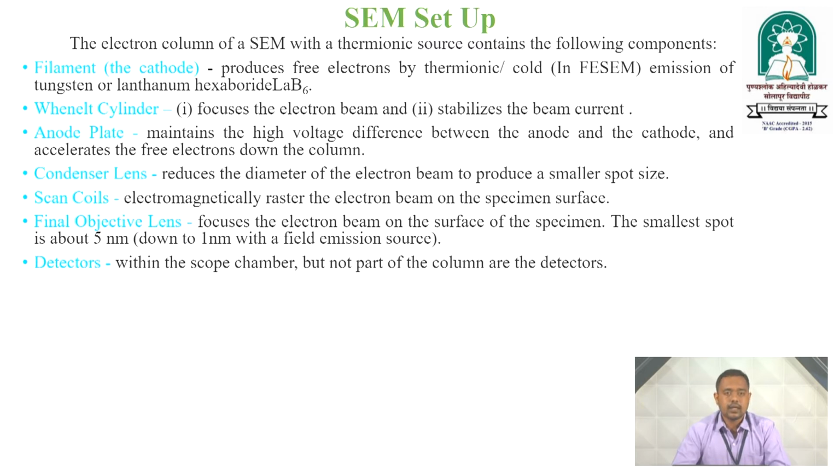Last but not least, there is the detector, which is within the scope of the chamber but not part of the column. The detector is situated inside the chamber only, but it is not part of the path of the electron beam.